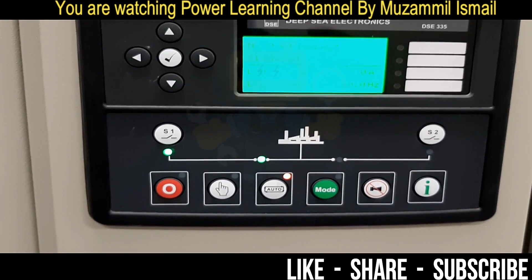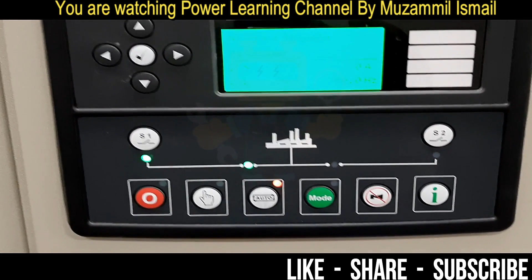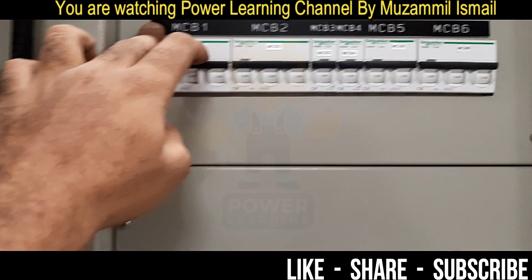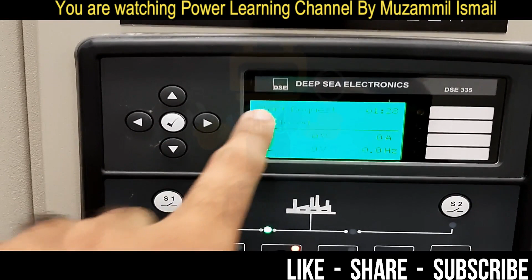Now we will start a demonstration of the auto test. We will turn off the mains sensing breaker. As you see, I turn off the power breaker and the S1 indication is now off, and it will give a start request command to the generator.